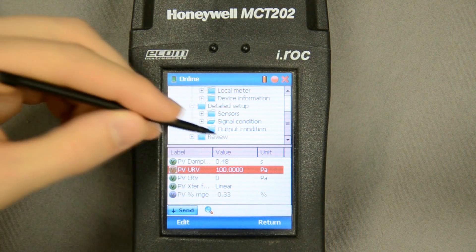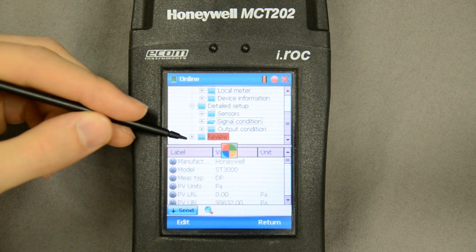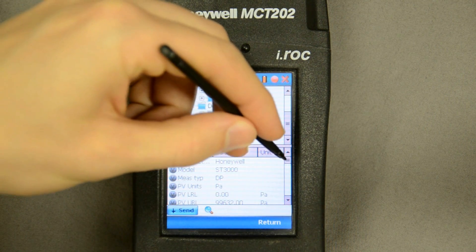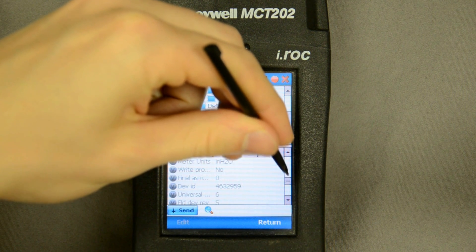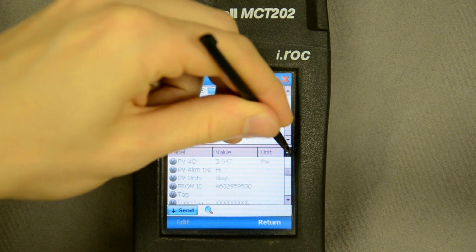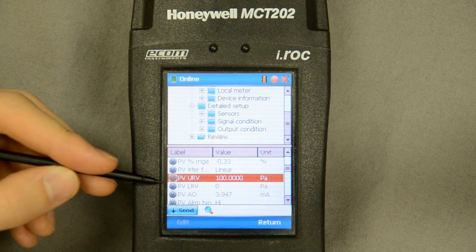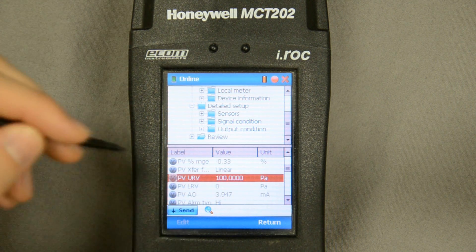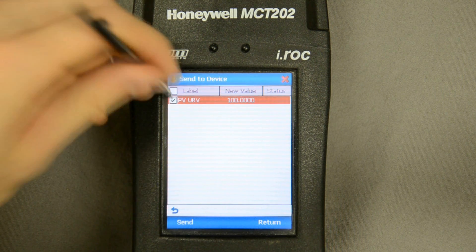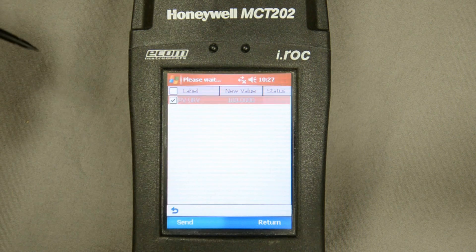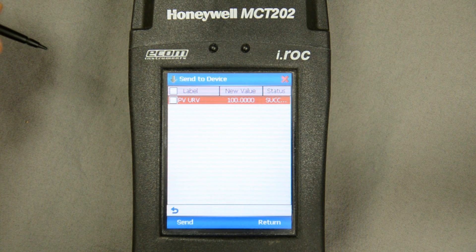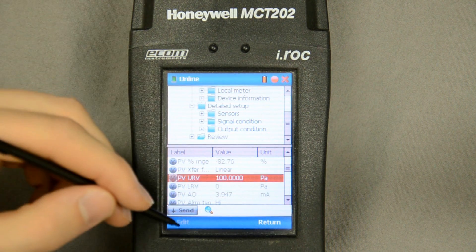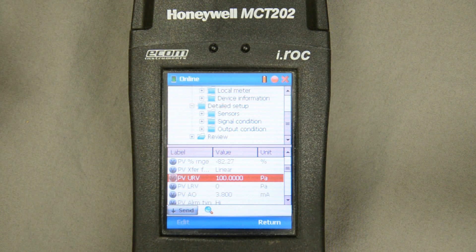Further down is every single piece of information related to the transmitter — the notes, the tag, all of it on one screen. I have something highlighted in yellow, which means two things: I made two changes to this transmitter but haven't written them to the transmitter yet. So the last thing I need to do is send those changes to the transmitter by checking these boxes, performing an execute that stores them to non-volatile memory. Once unplugged, the changes will be stored, not lost.